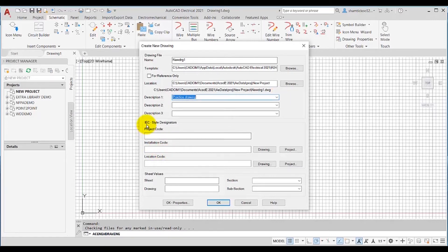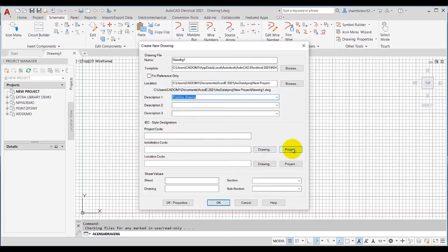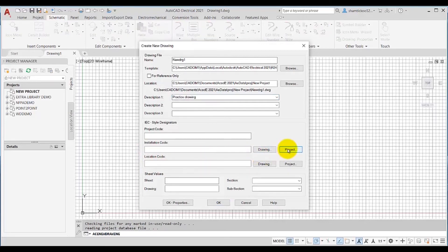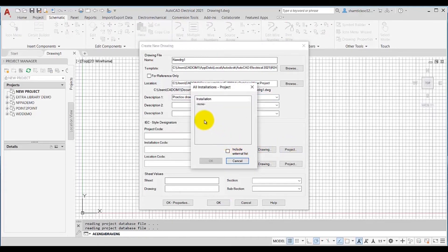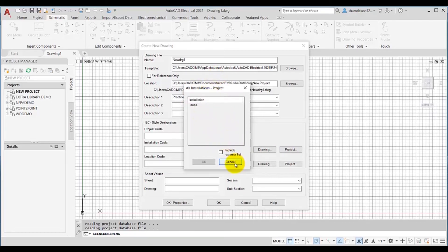In the IEC Style Designations area, you can add a project code in the Project Code edit box, and you can add installation code and location code in the Location Code edit boxes. Next to these installation and location codes, Drawing and Project buttons are available. When you choose the Project button, the installation codes already assigned to other drawings in the project will be displayed. Since this is a new project, no installation codes are assigned yet, so the installation dialog box is empty.